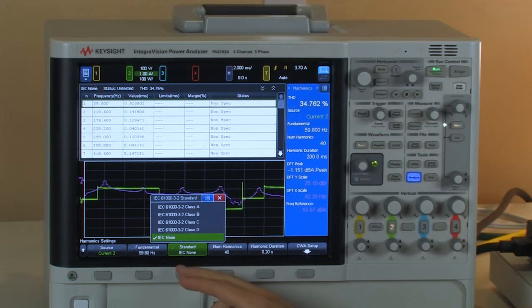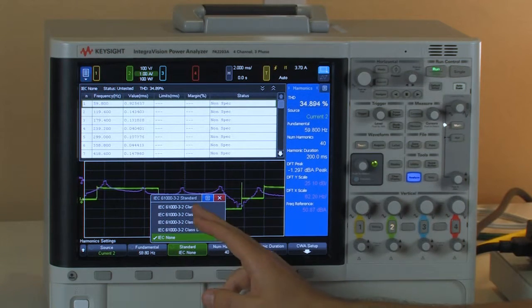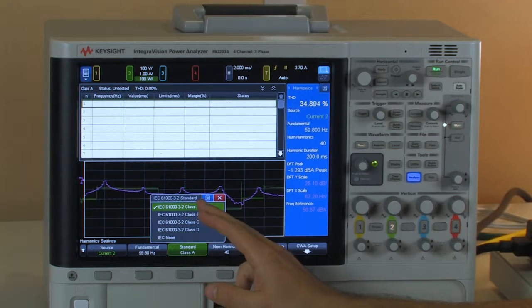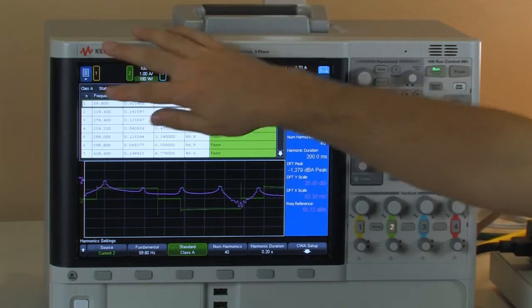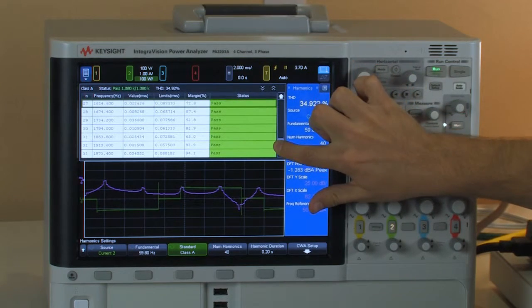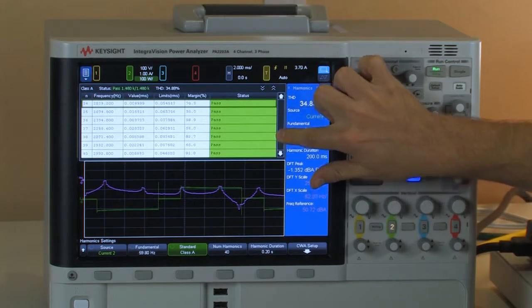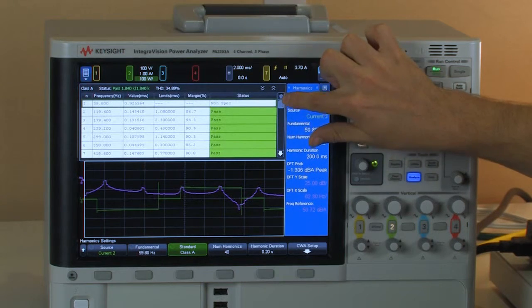So I'm going to go ahead and show you maybe a little bit of each one. So for class A, you can see the test reruns and I get all of my different harmonics up to the 40th harmonic. And you can see that I have nice green for passing.